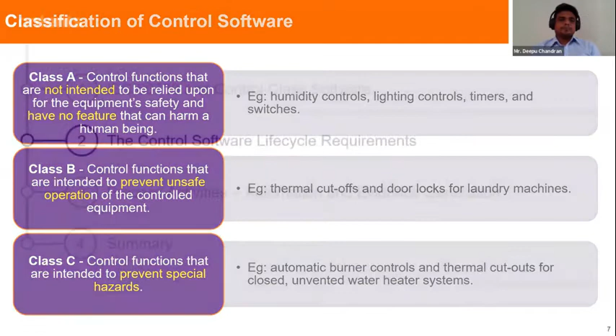In IEC 60730, if you look at the constructional requirement, the software requirement is called the software constructional requirement in Annex H of IEC 60730. It talks about software development activities which will ensure that the software that is developed will not damage the control's compliance with respect to other requirements of the standard. Other requirements may include the EMI or EMC requirements or thermal related requirements. All these are called other requirements from a standard point of view. And the malfunctioning of the software should not have a cascading effect on these other requirements. That is what the constructional requirements talk about.